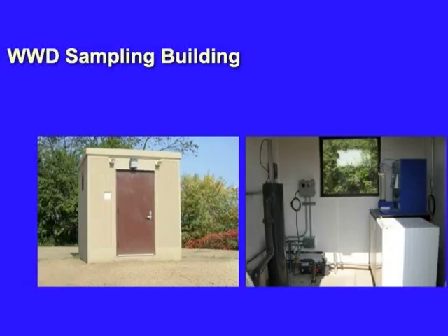You have a sample pump switch, which that sample pump should be in auto. That way you can start and stop it from the operator's workstation, okay? When you do a little troubleshooting, you can put it into hand and operate it there, start and stop it locally from the control at the pump. That pump's a self-priming centrifugal pump. The last event it did perform.